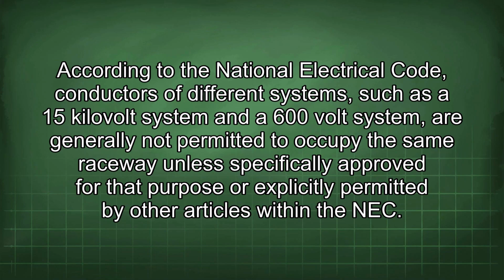According to the National Electrical Code, conductors of different systems, such as a 15 kV system and a 600 V system, are generally not permitted to occupy the same raceway unless specifically approved for that purpose or explicitly permitted by other articles within the NEC.